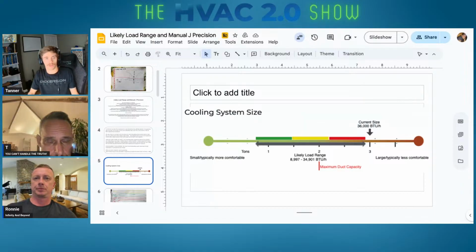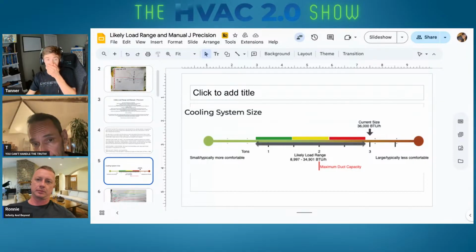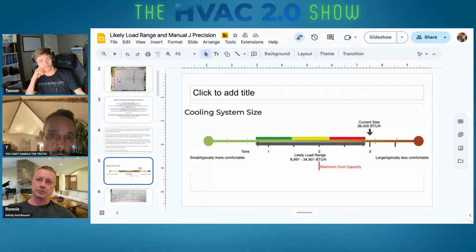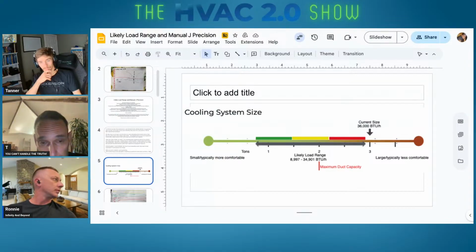Well, with all things being equal, if we're not changing the ductwork, we're not making big investments there, you might ask them the question, if they really want a 3-ton, do they want to spend 10 to $20,000 on new ductwork? Or if they were comfortable before, it's likely they were getting 2-ton of delivered capacity through that 2-ton of ductwork.